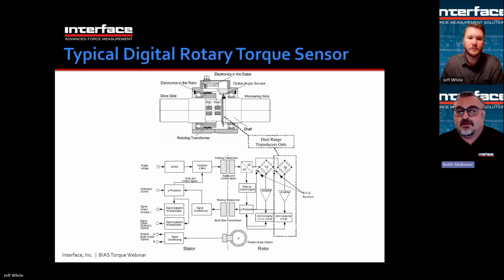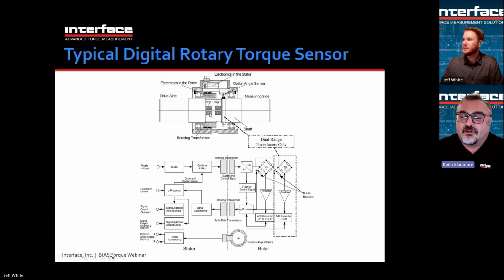Next slide. This is just an example of a digital rotary torque sensor. You can see there's a shaft, there's a drive side and a measuring side. The difference is there's more moment of inertia on the drive side, more mass, because the electronics are mounted to the drive side. There are some bearings. There's an induction coil called a rotating transformer, and that is for power and signal transfer. Then there's a microprocessor on the shaft, a strain gauge amplifier, an analog to digital converter, and then the digital signal is pulsed across a transformer back to the stator side, where it's further processed with a digital to analog converter to create a plus or minus 5 volt signal.